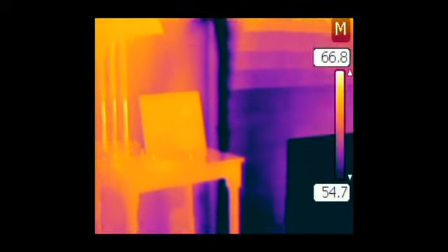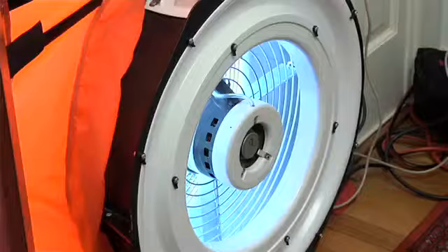It may be caulking the interior and the exterior. That's going to make enough of a difference. So, you know, a couple of dollars at the hardware store for some caulking, and you may be done. Yeah, that's a great way to demonstrate how the blower door and the infrared camera definitely work together, and they're two vital tools for performing an energy audit. Yeah, the two of them, there's nothing that can replace it. It's pretty amazing.